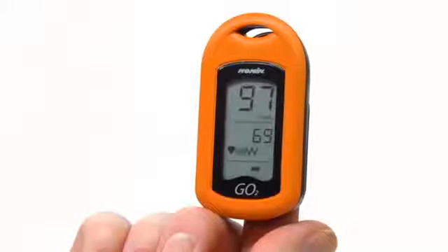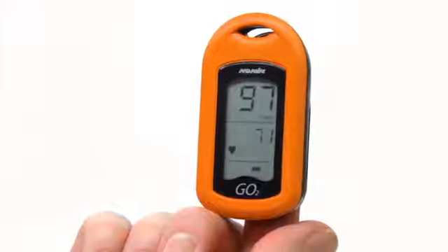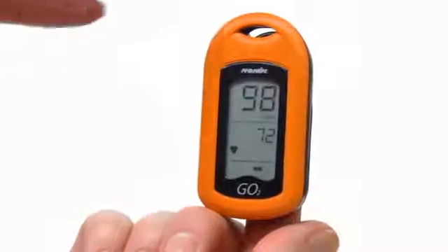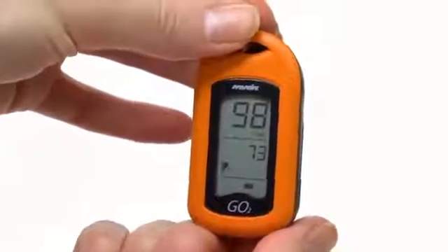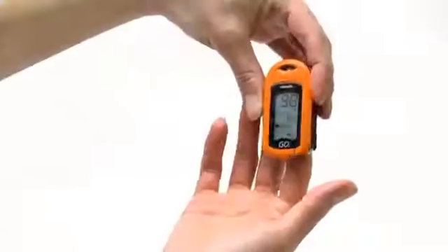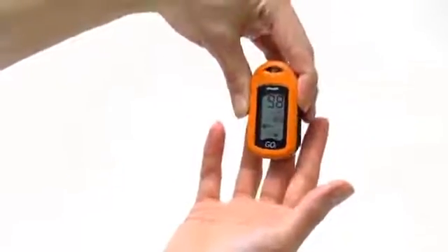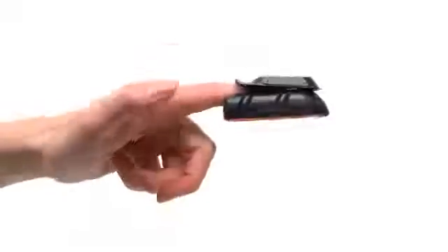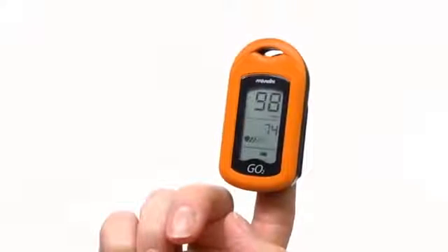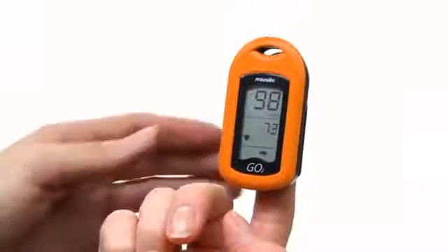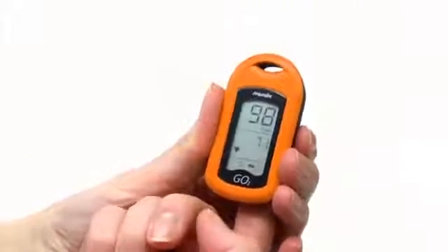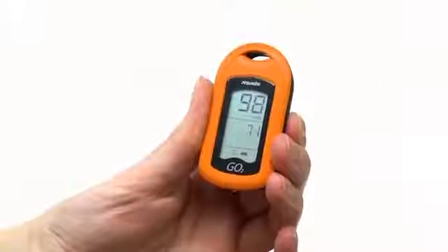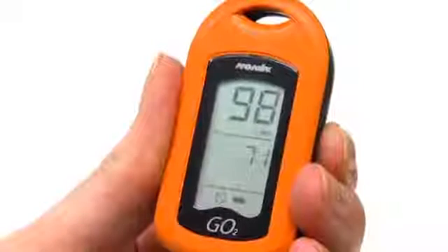If the pulse signal quality indicator is low, or you don't get a reading while you are using the oximeter, try repositioning the oximeter on the finger, warming the hand and reinserting the finger or moving to a different finger. Remember, proper placement is important for accurate readings. When you are ready to stop using the oximeter, simply remove the oximeter from your finger. You'll notice the sensor disconnect indicator appear. The GO² will turn itself off a few moments after it is removed from your finger.